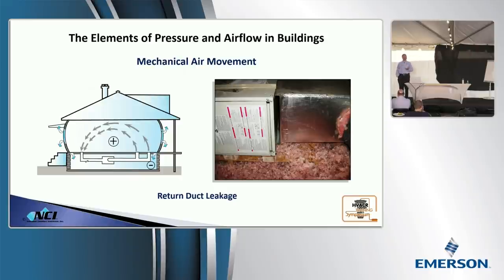Now, anybody in here doing duct sealing? I would hope every hand would go up. So here's something to keep in mind with duct sealing. Do you just randomly start grabbing mastic and slapping it on the ducts? You need to do one thing before you start sealing ducts: measure total external static pressure and compare it to the rated nameplate. See where it's at. If total external static pressure is high, those ducts may not need to be sealed.